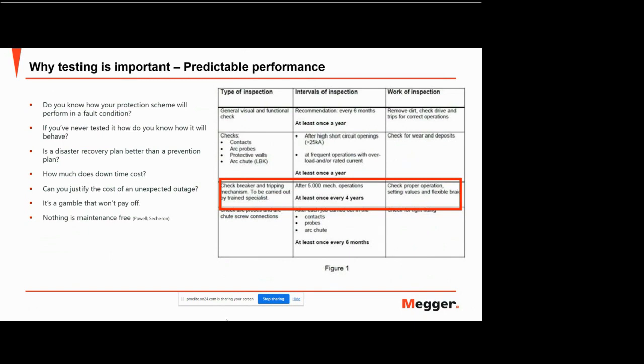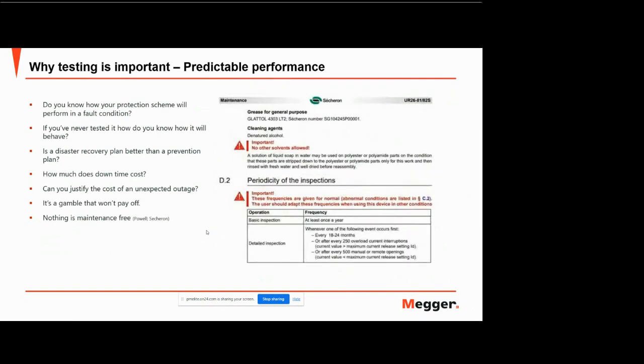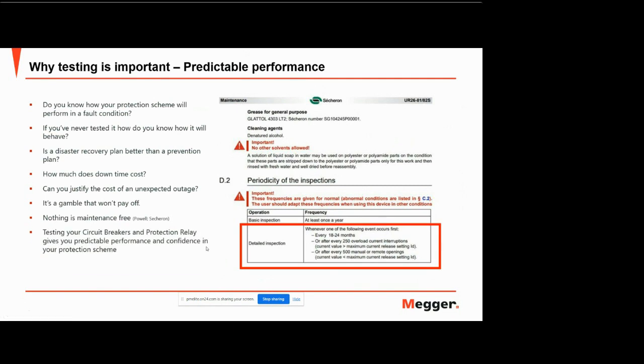correctly. Another main OEM manufacturer for DC high-speed circuit breakers, which is Secheron. So Secheron is the global leader for DC high-speed circuit breakers, and in their maintenance procedure, they specify that a detailed inspection is performed every 18 to 24 months, and that is to check to see that the overload current protection is working correctly, as well as other parameters as well. But that's the main purpose for a DC high-speed circuit breaker, is to make sure that it's tripping according to the current that's been set for that particular asset. So really, the main thing here is that if you test your DC high-speed circuit breakers and you test your protection relay, it gives you predictable performance, and it gives you the confidence that your protection scheme is working as expected and to specification.